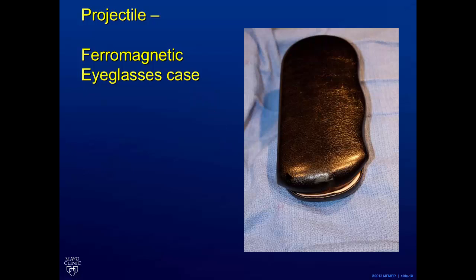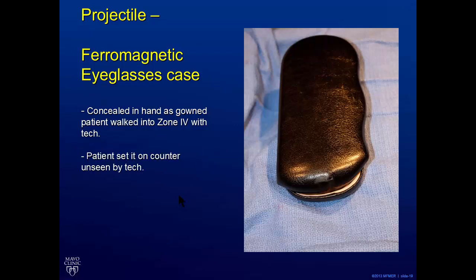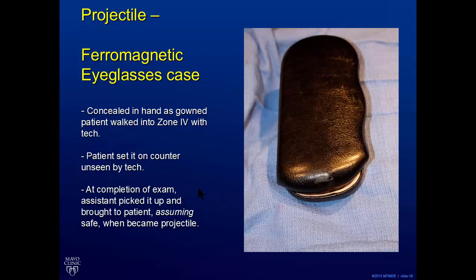I still have this on my desk — we use it for demonstrations with new techs. You can see the dent in it from when it flew towards a 3T magnet. The glasses case, containing glasses, was in the hands of a patient whom the tech allowed into the room with it. He put it down on the counter in the room and the tech just didn't see it. At the completion of the exam, a tech assistant walked in the room, saw the glasses case there, assumed it was safe because it was already in the room and hadn't flown yet. The assistant picked it up and started bringing it towards the patient, at which point it then decided to fly. The glasses broke but thankfully didn't hit anybody.